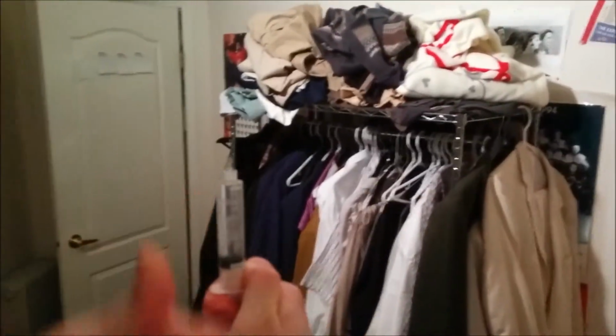We're going to just check. I'm basically pushing and pulling a few times to make sure that the access is good and will actually work. Sometimes things can get a little sticky. I mean, let's say there was a clot in the line, or let's say the Tego connector is worn out and needs to be changed. Just by pushing and pulling a few times, I can sort of get a sense of whether or not the access is working properly. And usually it is. If not, there are a few troubleshooting steps we can do. But for the most part, it's just a double check.